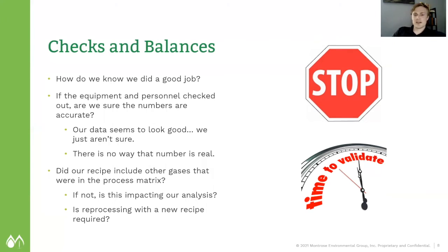Unfortunately, one of the things that we see, go into Excel, you can change the number. That's a poor way of handling the data. Once again, if you're collecting the single beams and the interferograms, a firm that is very reputable can go back. The FTIR, I always say, takes pictures of the spectra. We can take the data and we can look at it from the spectra point. We can do a manual validation.